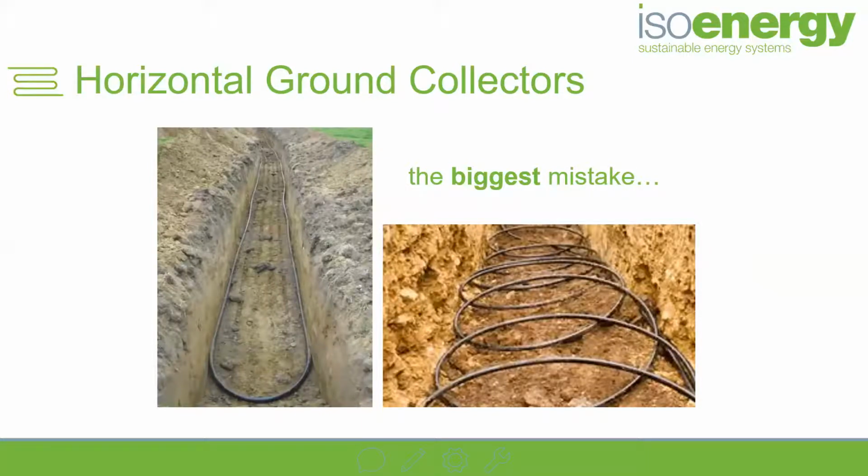Now that's fantastic if you're in the water, because water is moving, there's convection currents and energy moves more freely. So you're able to take a lot more energy out than you are out of the ground. In the ground, however, energy moves very slowly. So you need to make sure you're limiting the amount of energy you take out per square meter to what the earth can provide back into the ground in that local geology or soil type.